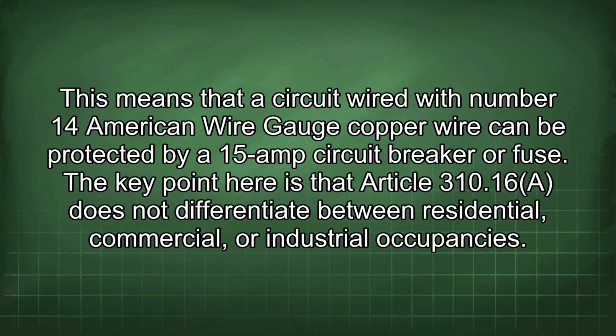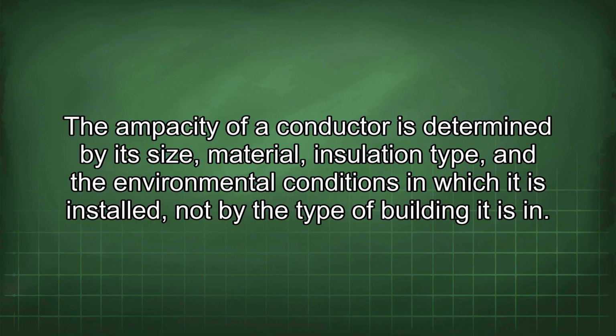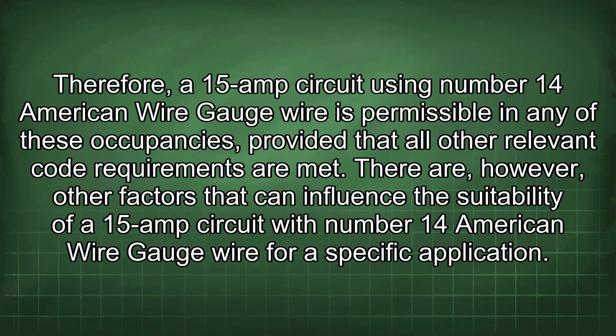This means that a circuit wired with number 14 American wire gauge copper wire can be protected by a 15 amp circuit breaker or fuse. The key point here is that Article 310.16 does not differentiate between residential, commercial, or industrial occupancies. The ampacity of a conductor is determined by its size, material, insulation type, and the environmental conditions in which it is installed, not by the type of building it is in. Therefore, a 15 amp circuit using number 14 American wire gauge wire is permissible in any of these occupancies, provided that all other relevant code requirements are met.